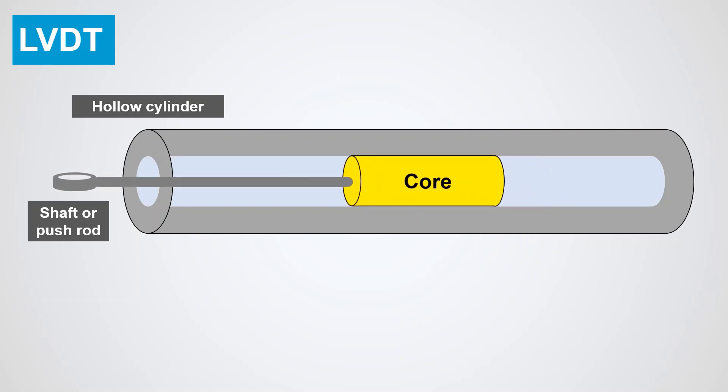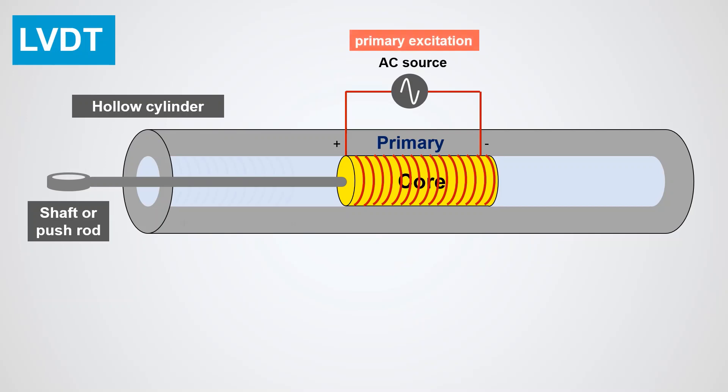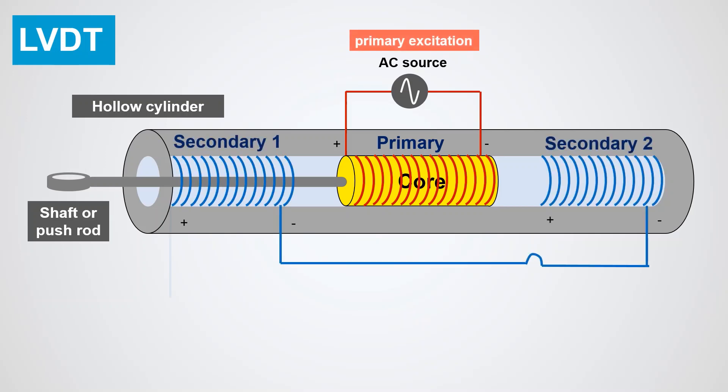A primary coil is wrapped around the middle of the hollow cylinder and is energized by constant amplitude AC source known as the primary excitation, while two secondary coils having equal number of turns are wrapped on either side of the cylinder at equal distances from the primary coil.